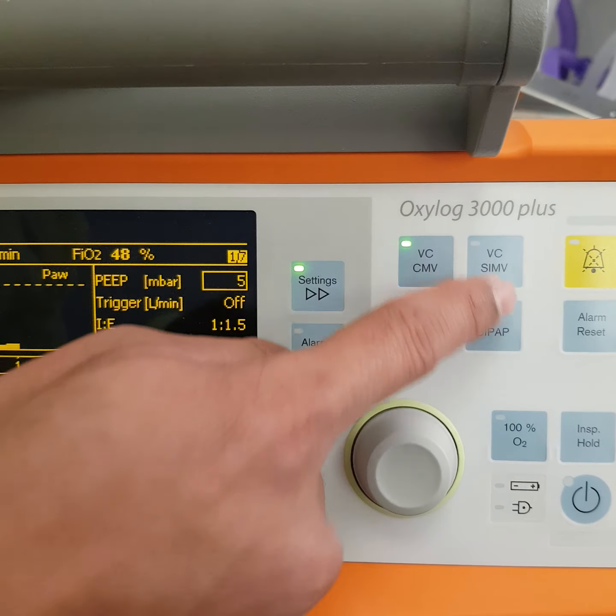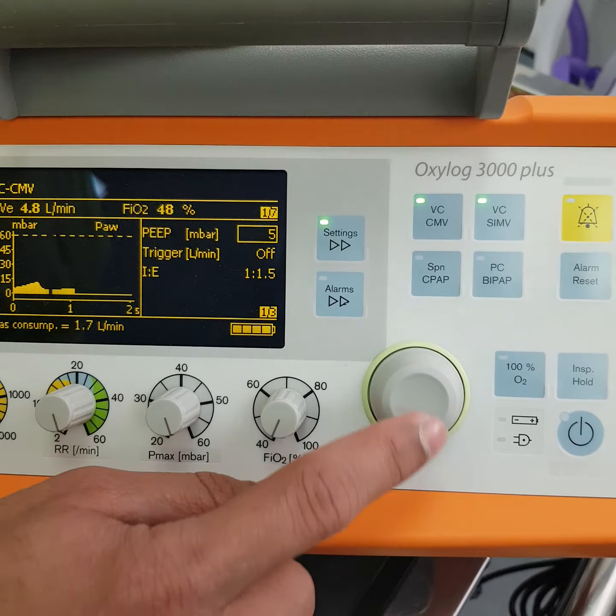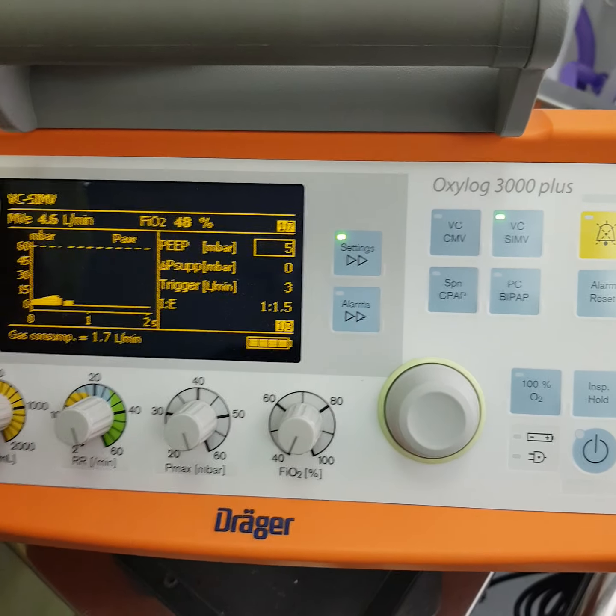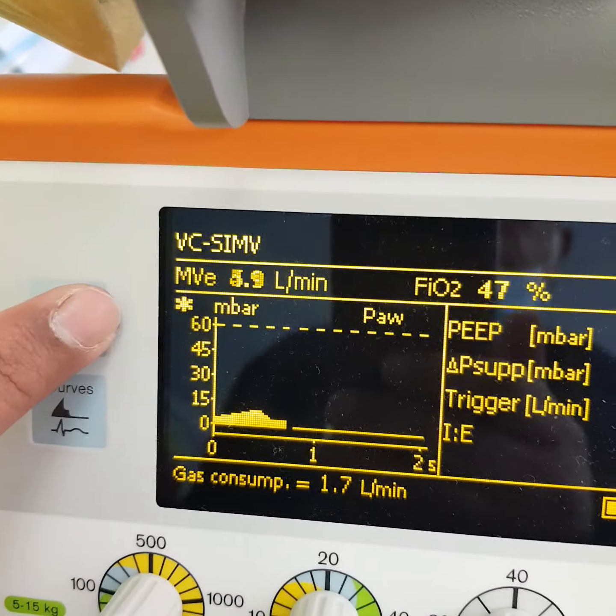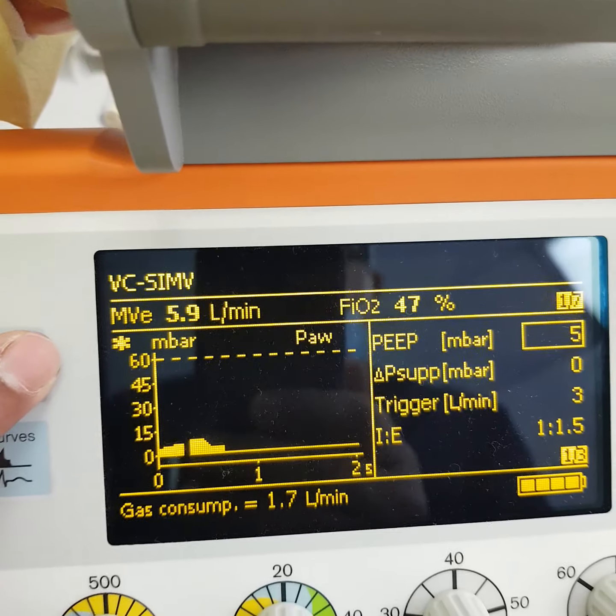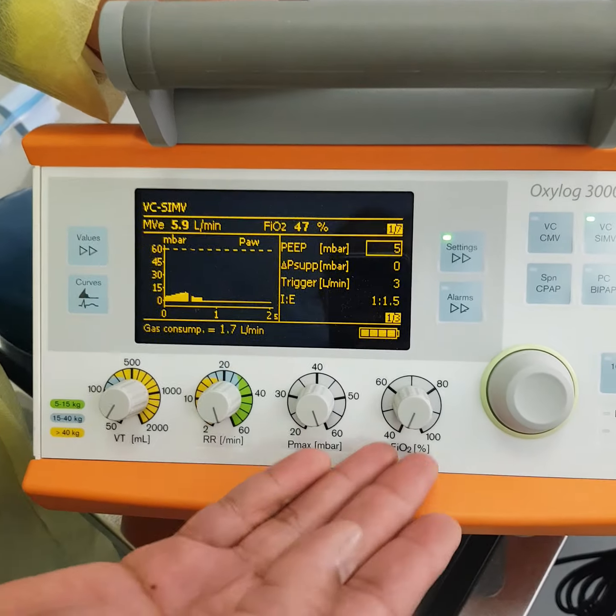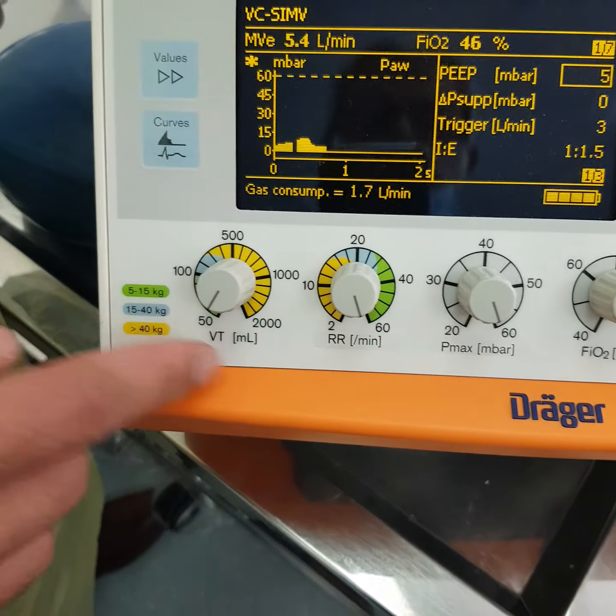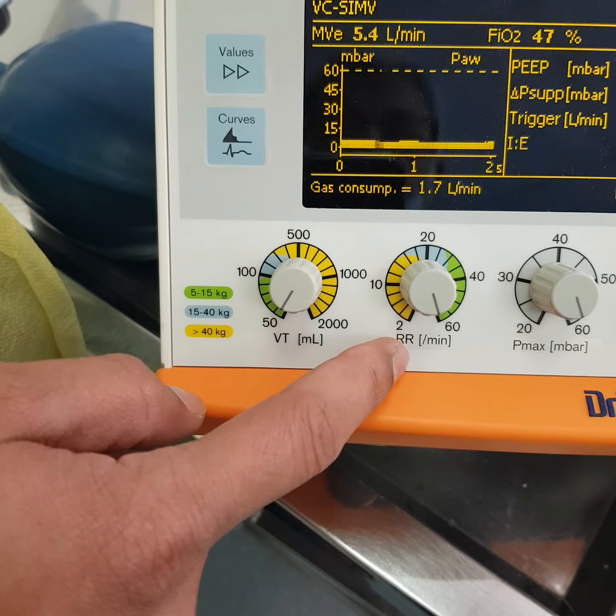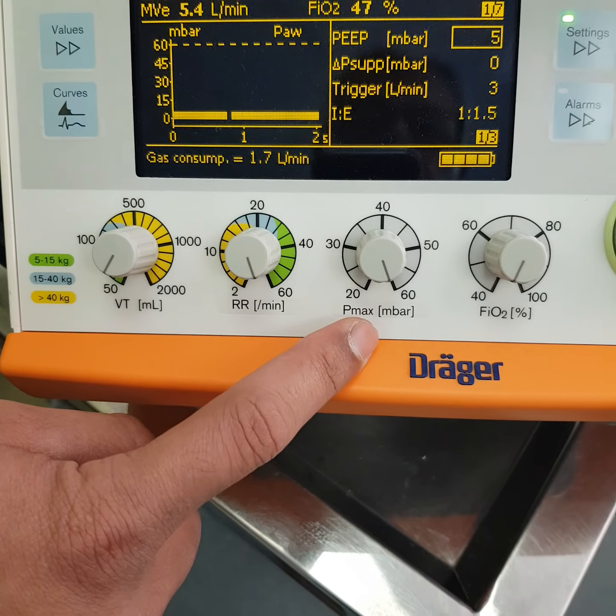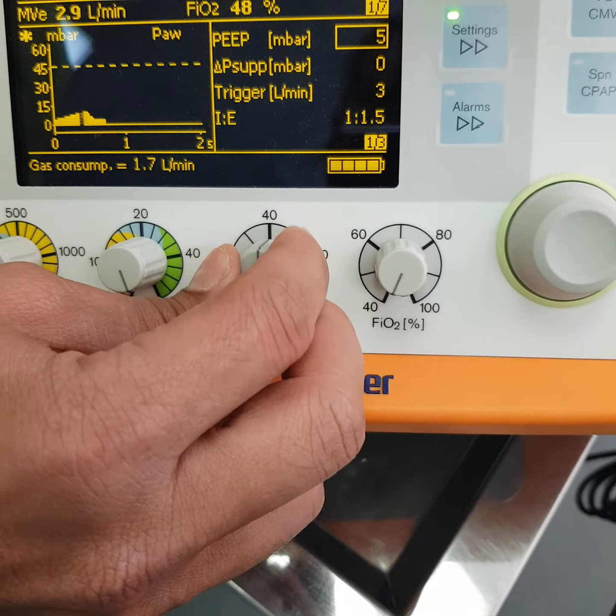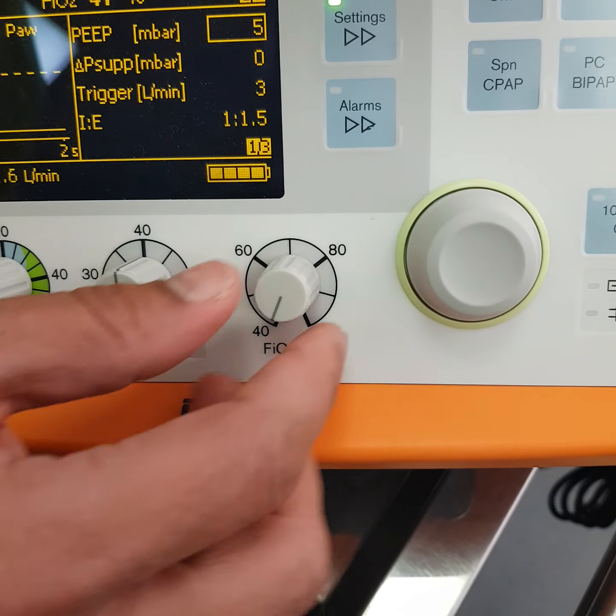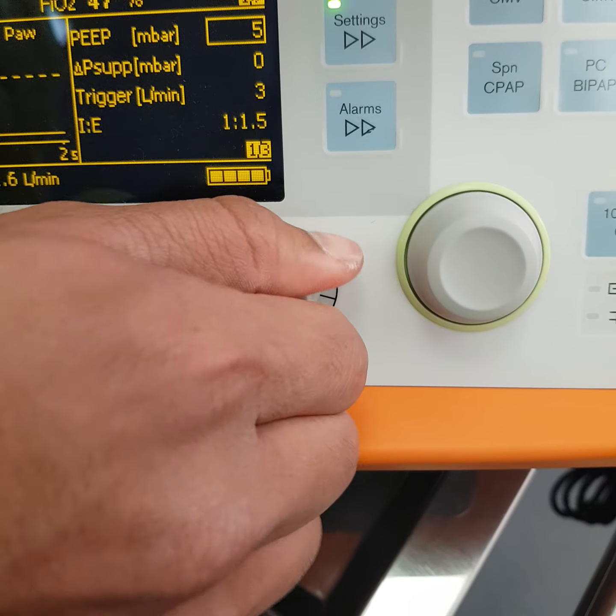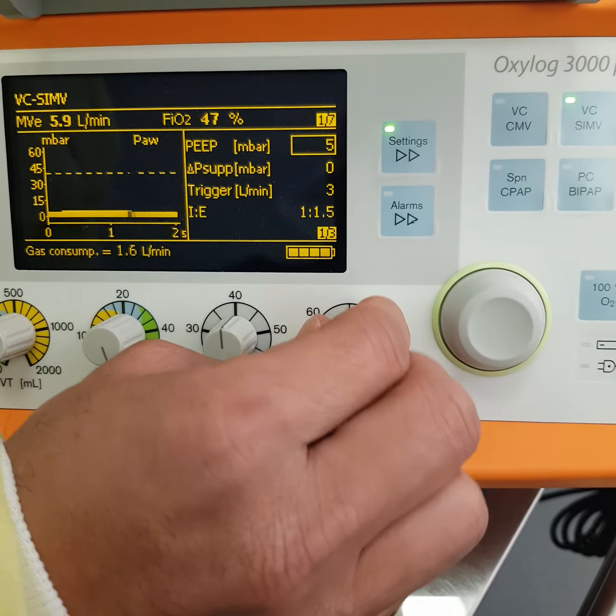So to shift from one mode to another, you are going to press any mode and confirm with the knob. It will immediately change the mode you are using for the specific patient. Once you have selected the mode, you are going to change the parameters underneath. These are all the key parameters. There is a tidal volume here and a respiratory rate, and this is the pressure maximum limit, so that you can limit the pressure maximum to avoid alarms. Also there is the oxygen percentage that you want to use, starting from 40 up to 100 percent. It can be adjusted with the rotary knob.